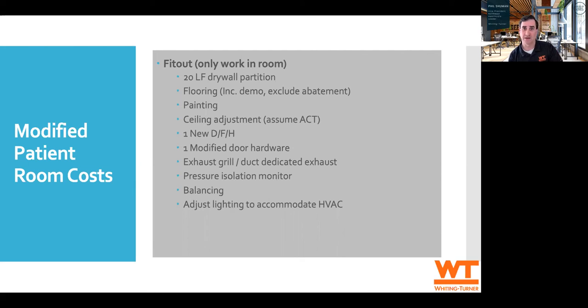You're going to be adding the ductwork, adding the pressure isolation monitor out in the corridor so that anyone prior to entering can verify that it's still negative. And then you're going to have to do some balancing as well.